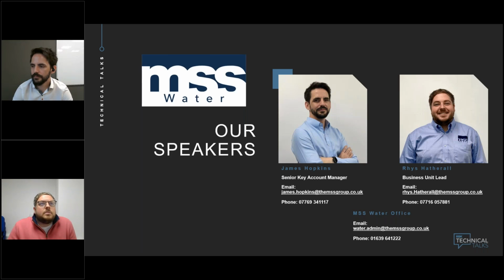Okay, next one. I've had dead legs picked up on my Legionella risk assessment, which I consider to be small. Are they essential to be removed? Sure. I think probably most people who are in charge of a premises will understand what a dead leg is. A dead leg is basically a piece of pipework that's been cut off or capped off when services have been changed. Or sometimes you might have a piece of pipework that's installed to allow for something to be installed in the future. Basically, in a nutshell, it is an area of low flow.